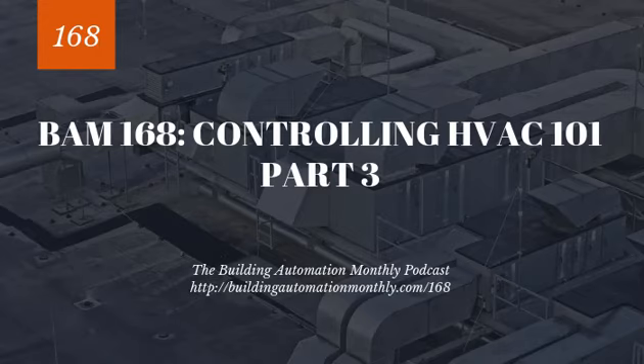Now, tower fans can be constant volume or variable volume. The nice thing about variable volume fans is that you can actually partially load towers. You can run multiple towers in unison at partial speeds, taking advantage of that fan curve so that you're optimizing your efficiency while controlling temperature. Whenever you're dealing with cooling water fans, you are going to be controlling to a condenser water set point, and that set point is actually going to be driving your fan speed. So you're typically going to want to have a medium speed loop in order to run that.